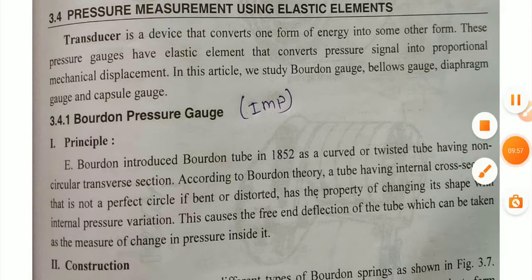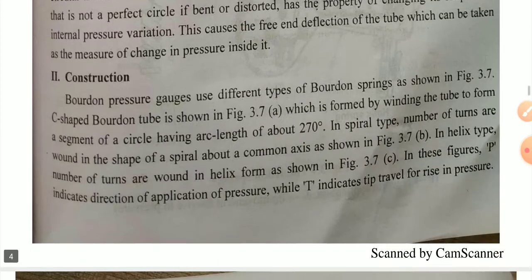This is the most important theory. The Bourdon pressure gauge is important, and there is a 100% chance it will be asked in GTU. Bourdon introduced in 1852 a curved or twisted tube having a non-circular transverse section. According to Bourdon's theory, a tube having an internal cross section that is not a perfect circle, if bent or distorted, has the property of changing its shape with internal pressure variation. This causes the free end deflection of the tube, which can be taken as the measure of change in pressure inside it.